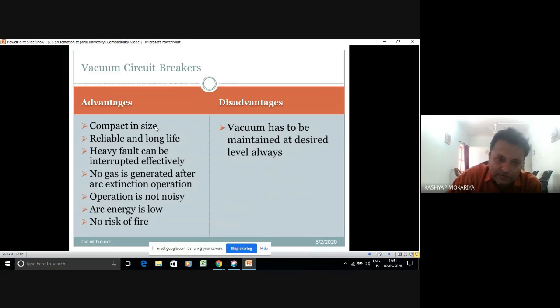Advantages: compact in size, obviously very compact, reliable and long life. Heavy faults can be interrupted effectively. No gas is generated after the arc extinction operation. Operation is not noisy, very quiet operation. Arc energy is low, no risk of fire. Disadvantage: vacuum has to be maintained at the desired level always. In the vacuum bottle, at the bottom side, there was one white spot or dot, we were told in industry. So when we go for preventive maintenance, we were told that whatever the vacuum level you see in your visual observation, you have to note it in the PM sheet, whether the vacuum level was okay or not. And according to my remarks, the concluding actions were taken.